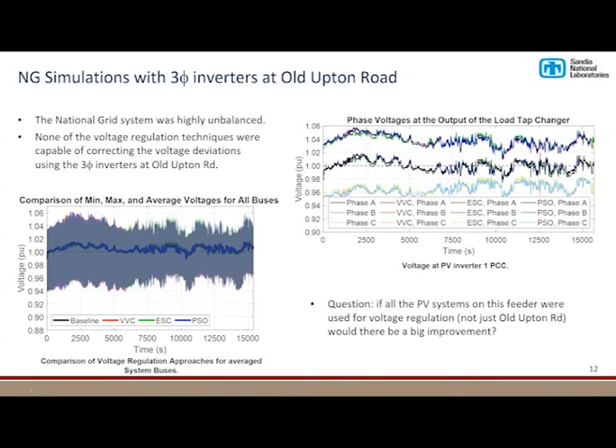And so when we ran each of the use cases, everything pretty much stayed more or less the same, right? It couldn't improve the voltage on this particular feeder, even though it was imbalanced, because when you change the power factor for these devices, it changes the power factor on each phase. And so if you move it up or down, it actually gets worse overall. And so we ran into a situation that we couldn't solve for that.